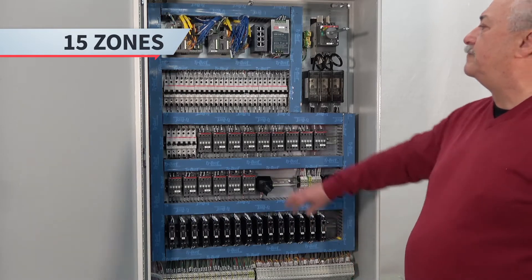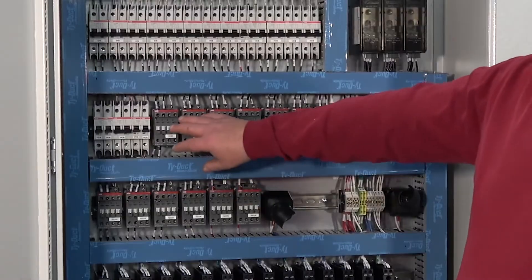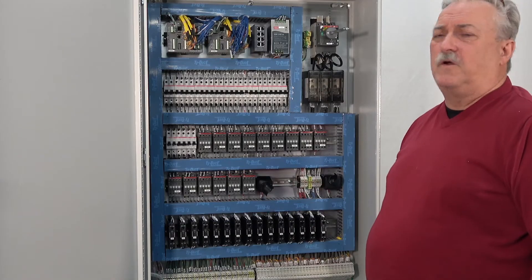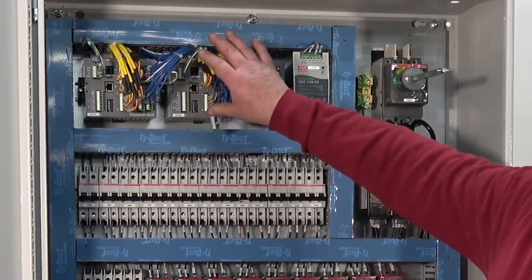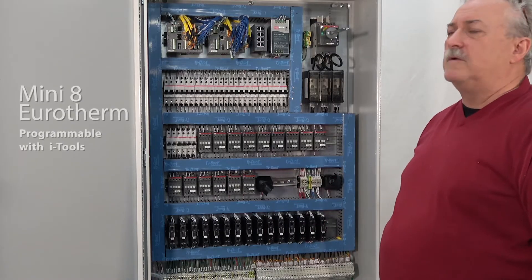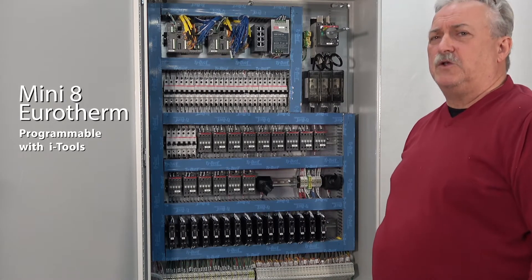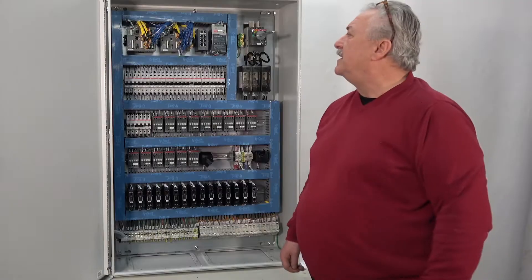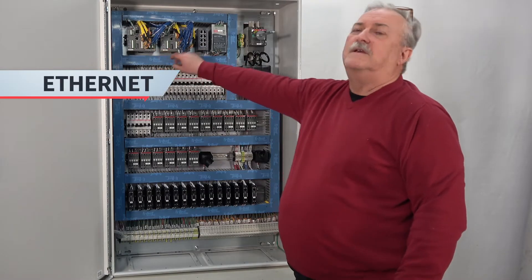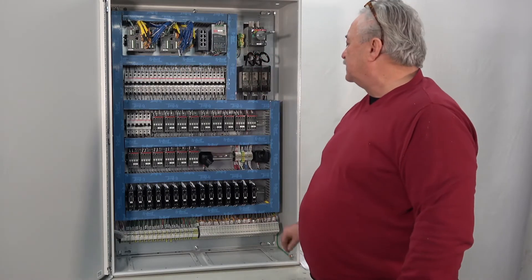All zones are protected with a circuit breaker and an alarm contactor for a high-temperature alarm. This system is controlled by two Mini-8 Eurotherm products. The Mini-8 Eurotherm is programmable with iTools, which is a Eurotherm software. They are also Ethernet connected and controlled with a 24 volt circuit.